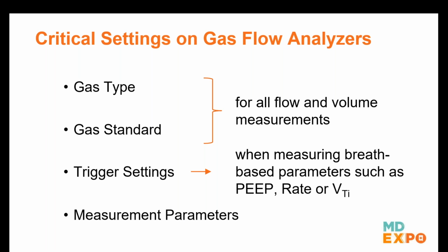Different name, same measurement. Okay, so knowing all those measurements and then making sure that you're also using the correct unit of measure for each of those measurements, all very important. Here in the US, we usually use mostly centimeters of water for pressure, liters per minute, or maybe milliliters per minute for flow. But it's important that you're using the correct unit of measure as well as the correct measurement setting. Any questions so far?